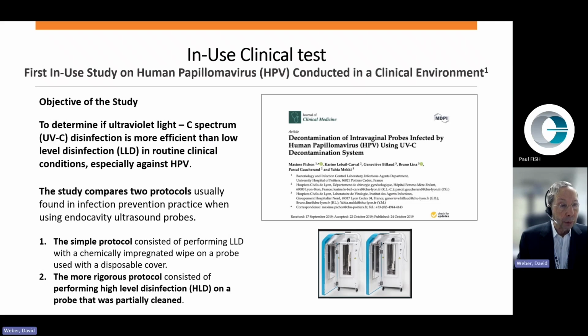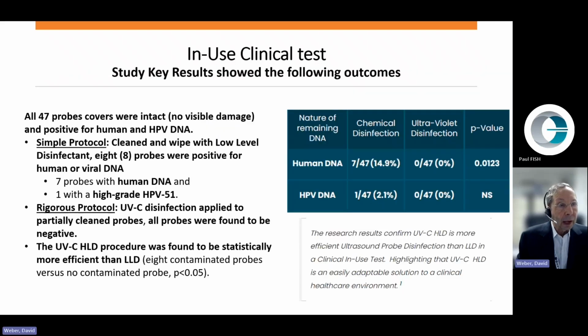The study compared two protocols usually found in infection prevention practice when using endocavity ultrasound probes. The simple protocol consisted of performing low-level disinfection with a chemically impregnated wipe on a probe used with a disposable cover. The more rigorous protocol consisted of performing high-level disinfection on a probe that was partially cleaned. To the right, you can see this paper by Maxime Pinchon, titled Decontamination of Intravaginal Probes Infected by HPV Using UVC Decontamination System. Now, the key results of this study showed the following outcomes.